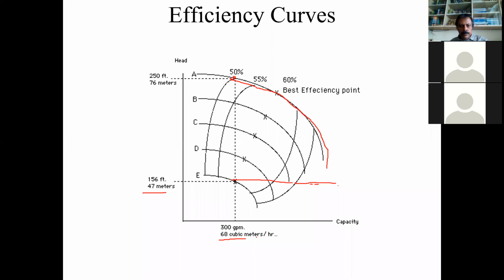Okay. Now, if you choose B, C, D, the same thing is going to happen. You're going to throttle. But if you choose pump E, when you operate it, it will deliver 68 meter cube per hour at 47 meter head. So if you use pump E, you don't need to throttle. You get the desired requirements without throttling the pump.